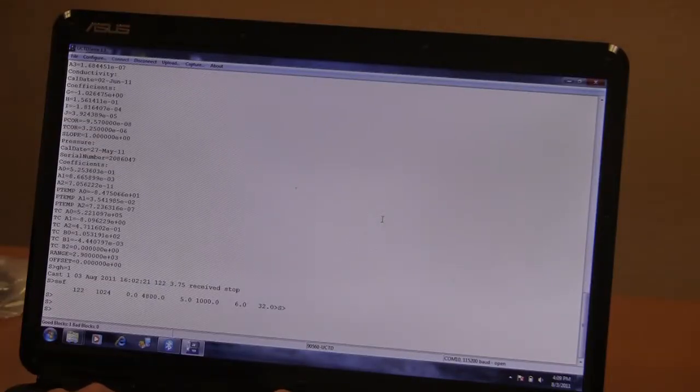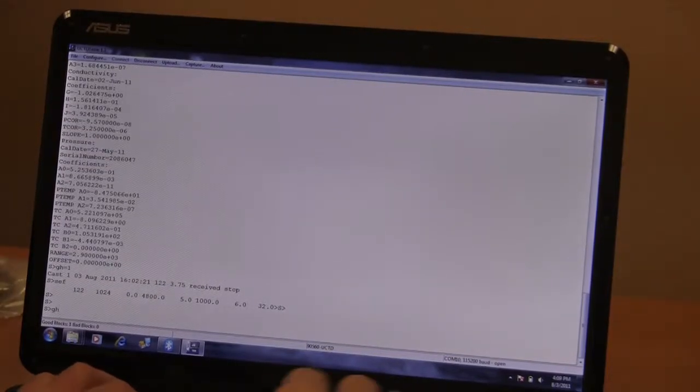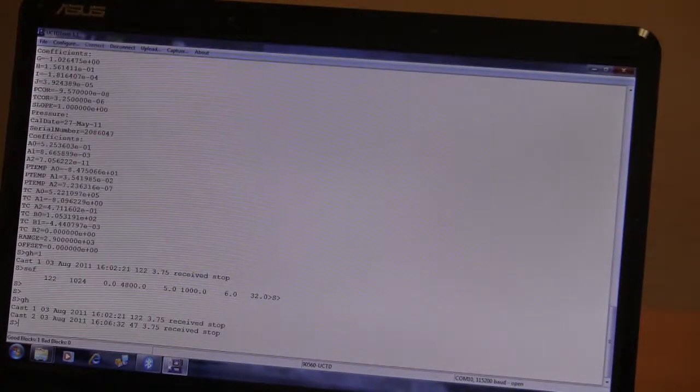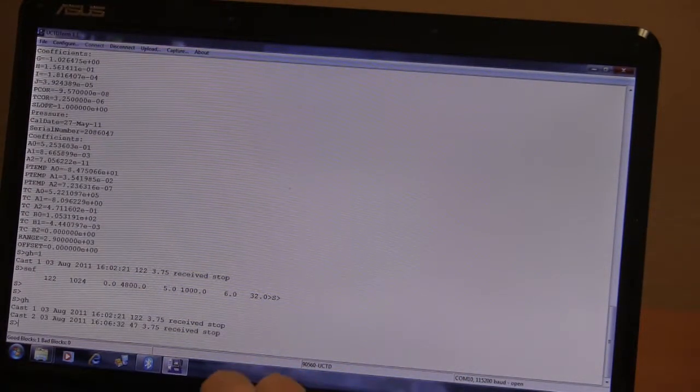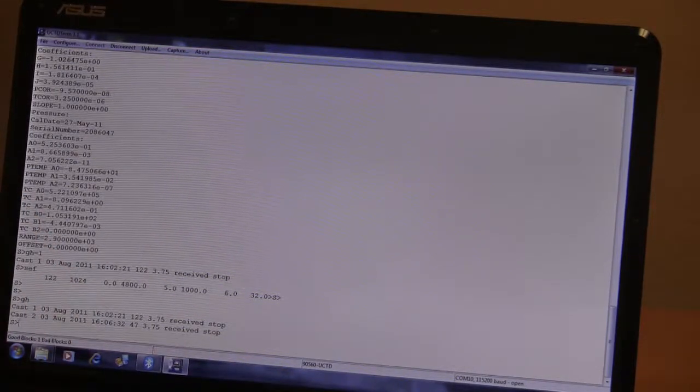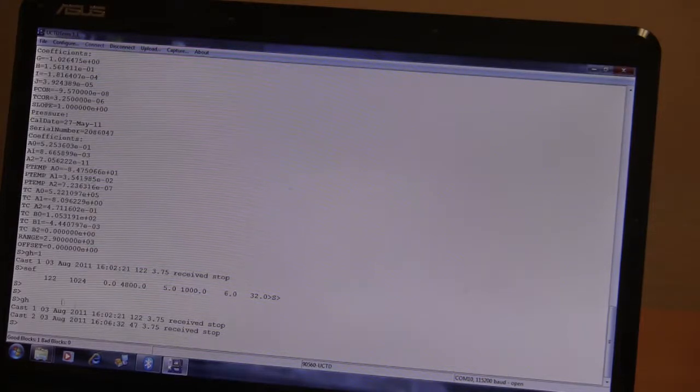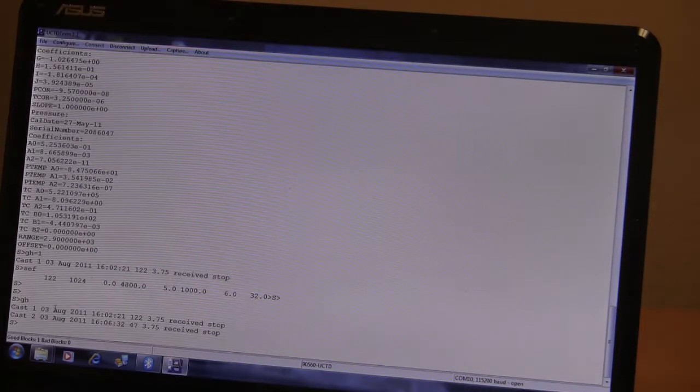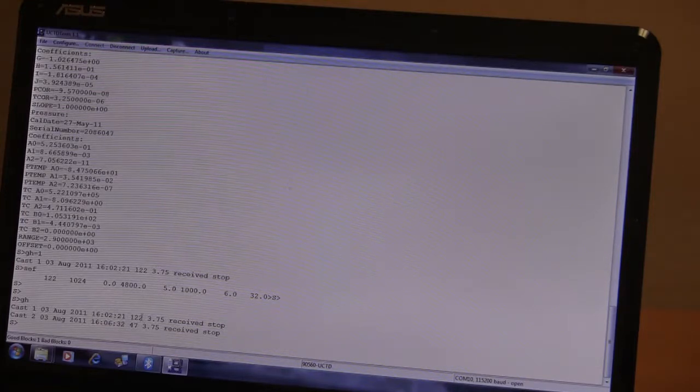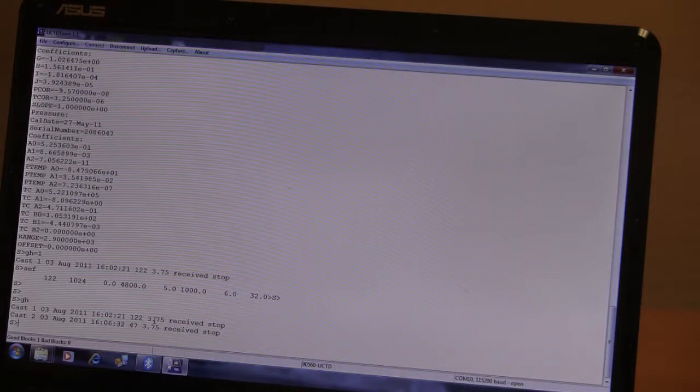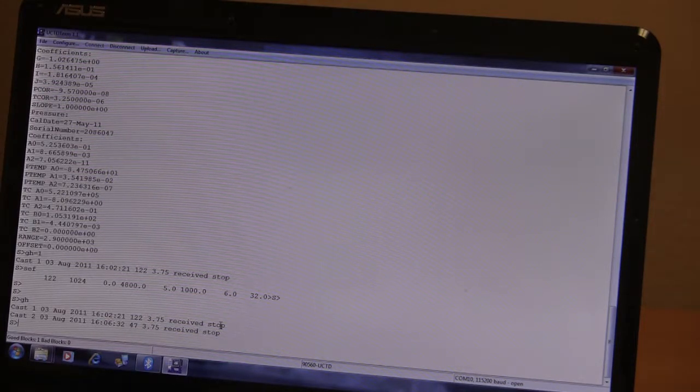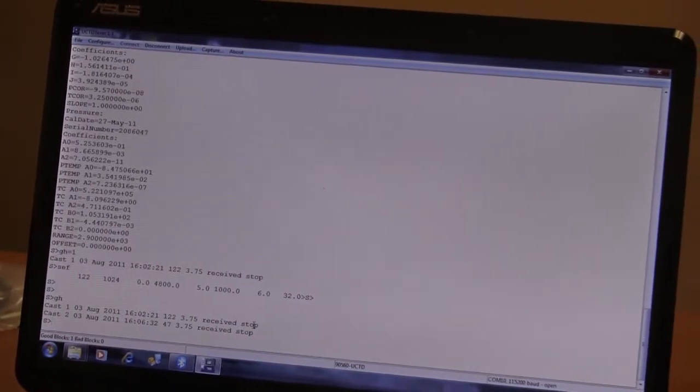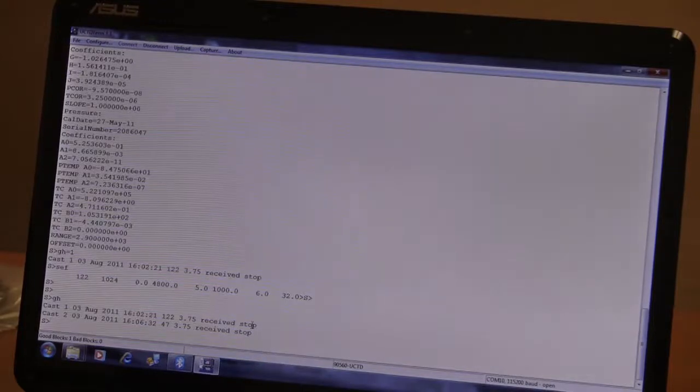In order to find out what data was stored on the probe, we issue the get header command, GH. That lists the number of profiles. In this case, it's only two. That's typically the situation when you get a brand new probe. It shows you cast one, recorded on August 3rd, and the time. The number of samples in that profile. The battery voltage when it was recorded. And in this case, it also tells you why the recording stopped. It's because I cycled the magnetic plug, rather than let the probe continue to record for a full 100 seconds.